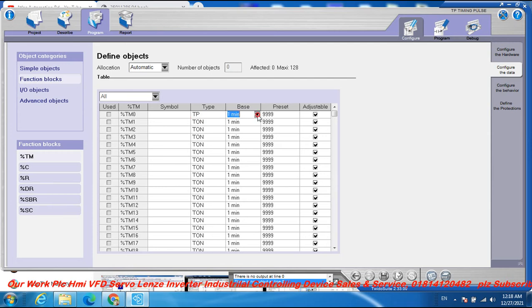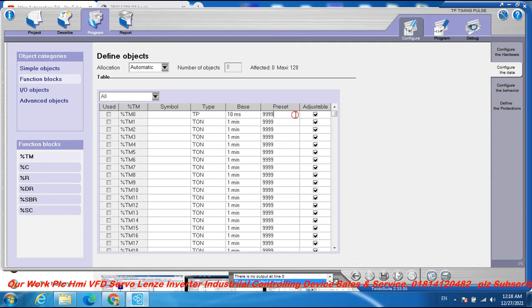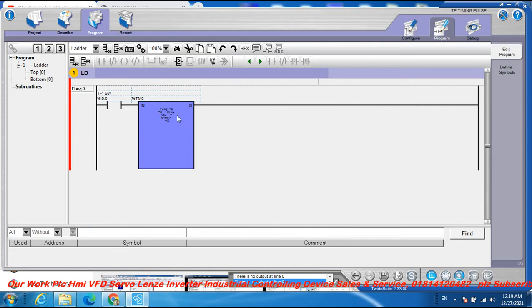Set the time base to 10 milliseconds. Set the preset value to 100. So the timer base is 10 milliseconds and the preset is 100, giving a timing pulse duration of 1 second.